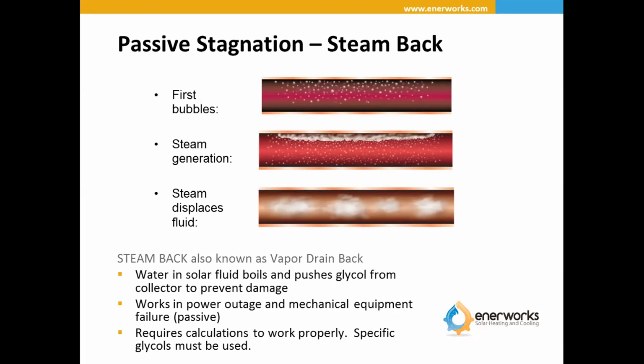And the other advantage of doing this is it keeps your system fairly low pressure. Some of these systems are only pressurized to 25, 30 PSI. The taller the building is, the higher you have to pressurize it, but this allows you to keep the design with a much lower pressure in the system. This works in the event of a power failure, a load disruption, or a mechanical failure. In some cases, that mechanical failure might be as simple as animals chewing on, like we've had squirrels chew on sensor cables, and so your temperature sensor is no longer reading correctly. So this is a simple but effective way to prevent damage to the system. It's something that we've used for 15 years, but it's been used extensively in Europe for probably twice as long as that.